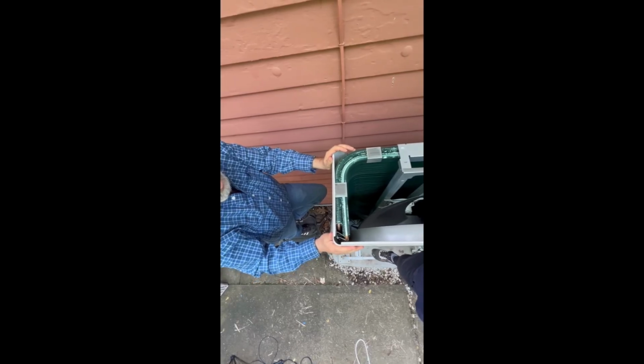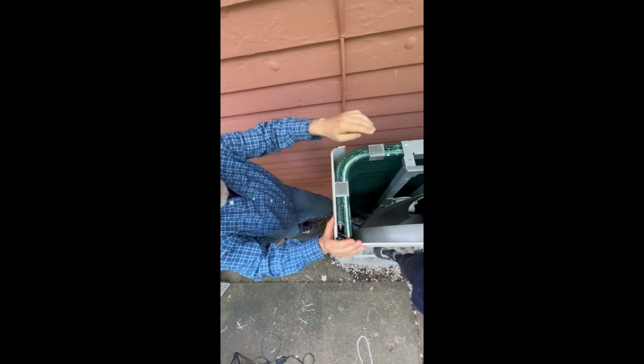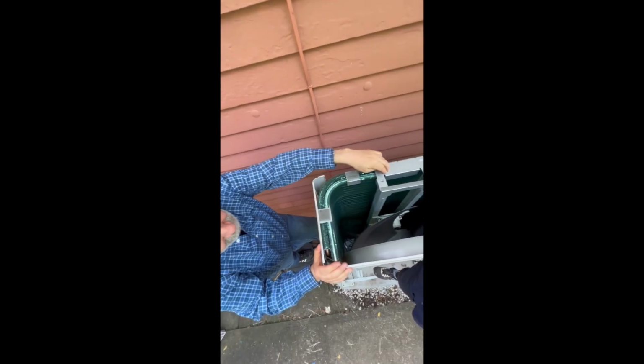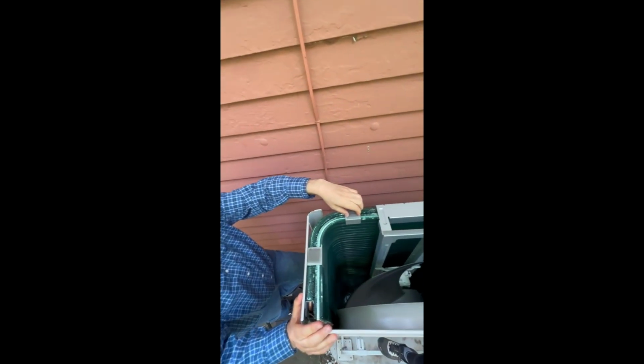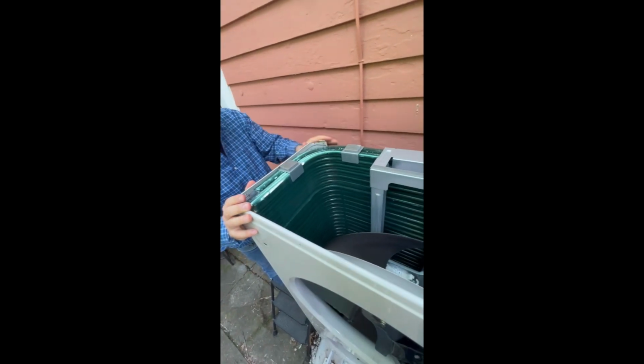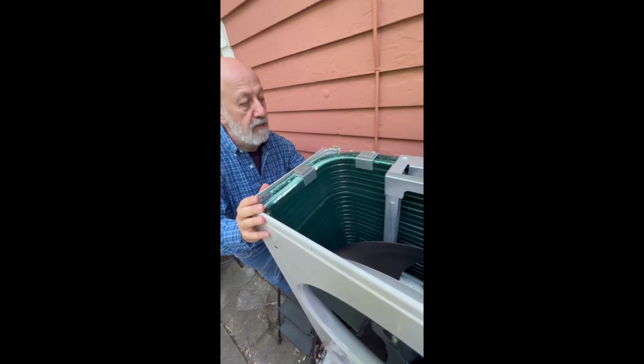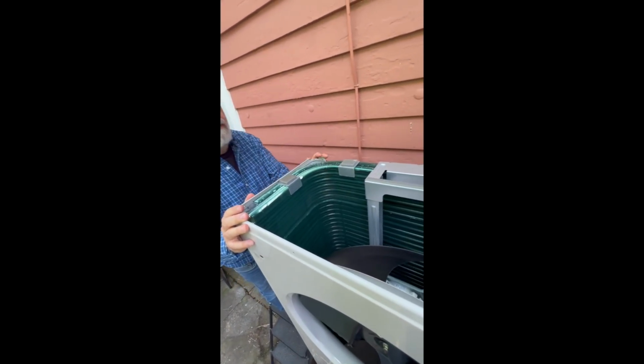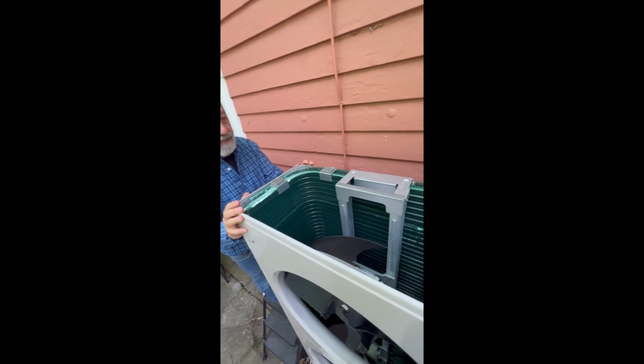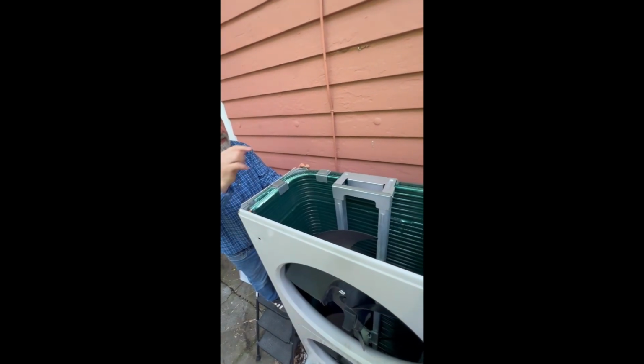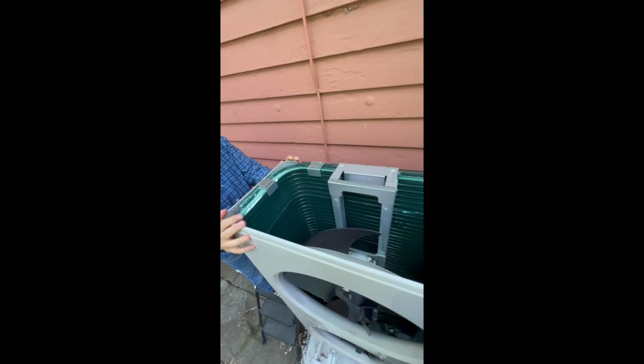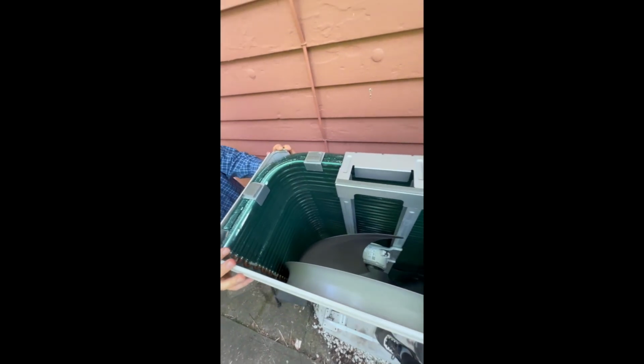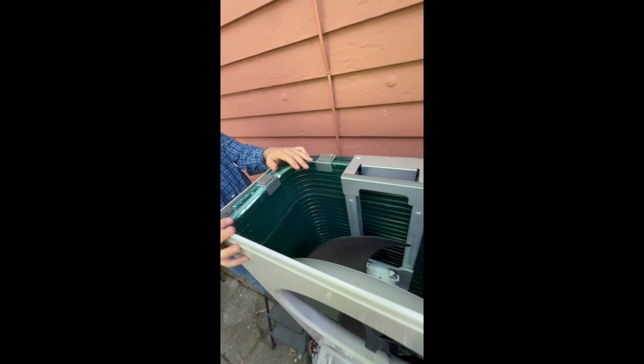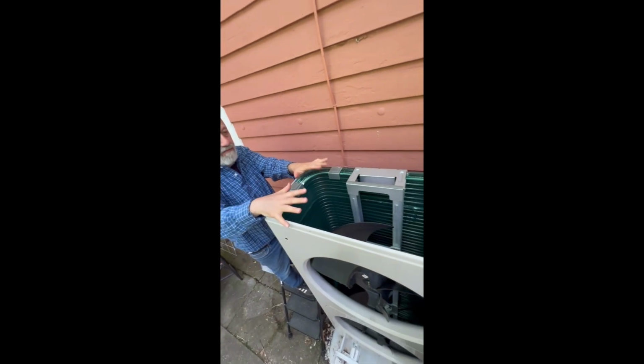The second biggest area of bypass was over the top of the coil. We've got this fan motor bracket and we've got these spacers, but this is about 1/4 inch to 3/8 of an inch of total gap. The air comes over the top and into the fan. We had also air bypass at the bottom of the coil underneath it, and that was measurable. We've identified the biggest air bypasses so far in this fan section.